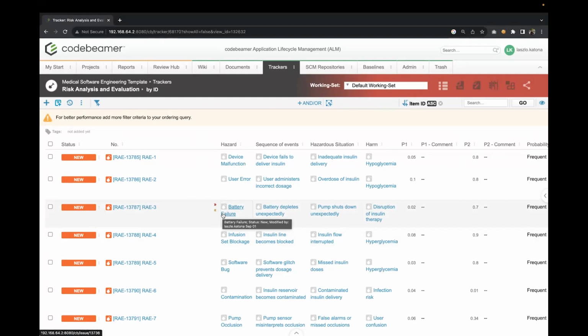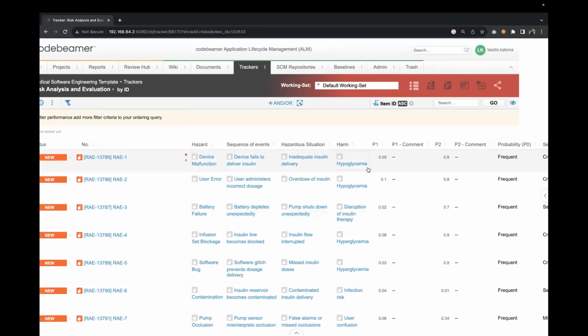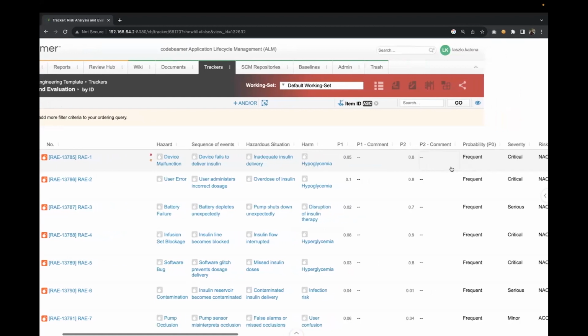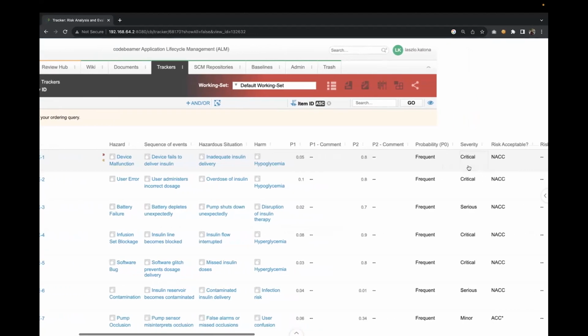The big difference compared to an Excel spreadsheet is the ease of traceability, because those containers that we've seen before are actually housing the hazards, sequence of events, hazardous situations, and harms that we have identified. They are all traceable to each other. It is very easy to use a tool called the Traceability Browser to run reports to identify, for example, the potential impact of a change in a risk control measure. We do have the ability to document P1, P2 values, and Codebeamer is capable, based on configuration, to automatically calculate the P0 value, and together with severity, it can calculate whether the risk is acceptable or not.